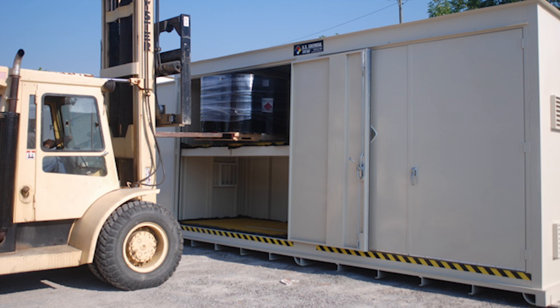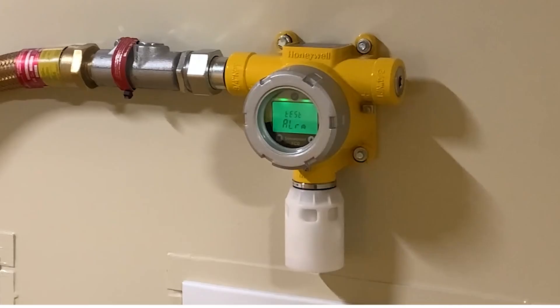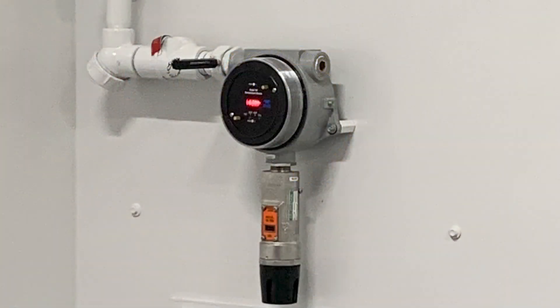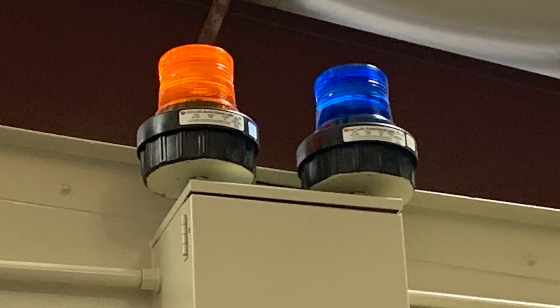How should you safely store ammonia? Due to its explosion risk, store ammonia in a fire-rated chemical storage building. Regulators may require this depending on how far the ammonia storage location is from an occupied building. U.S. Chemical offers two- and four-hour rated fire buildings. Use an ammonia gas detector in the building to pick up the release of ammonia vapors; this will identify a leak and notify the relevant people via an alarm.